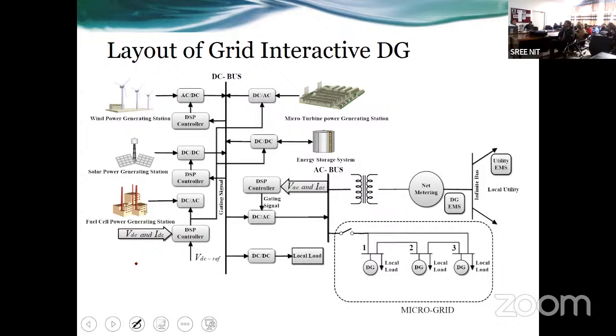It is just like different sources are injecting current at the DC bus. And then from that DC bus, that current has to be extracted and given to the AC bus. And that has to be done with the help of a grid interactive or grid tied inverter. So grid tied inverters are required, which are going to connect it to the main grid.